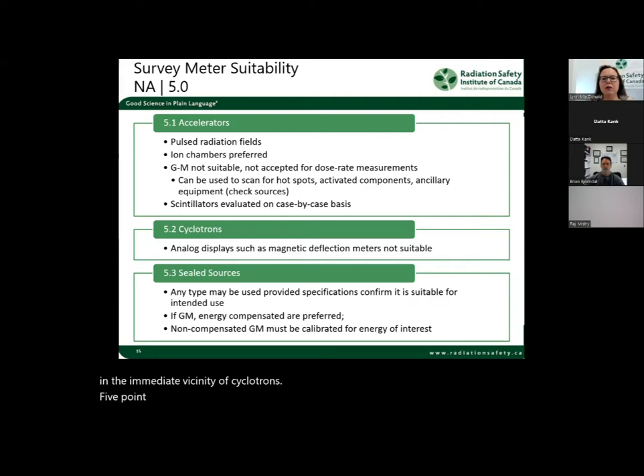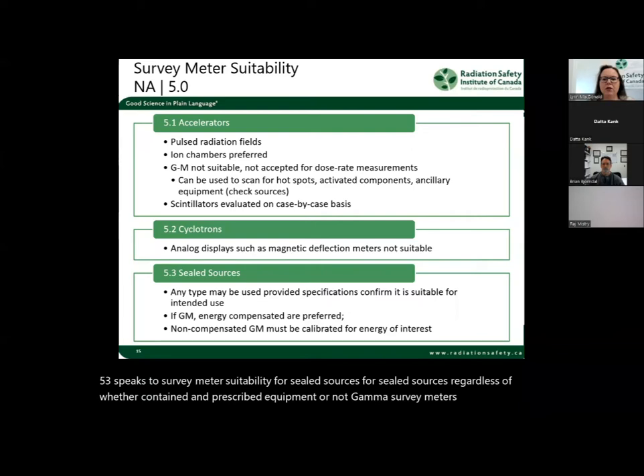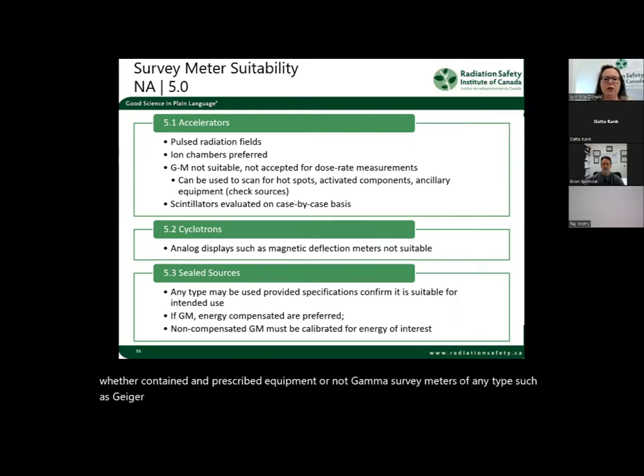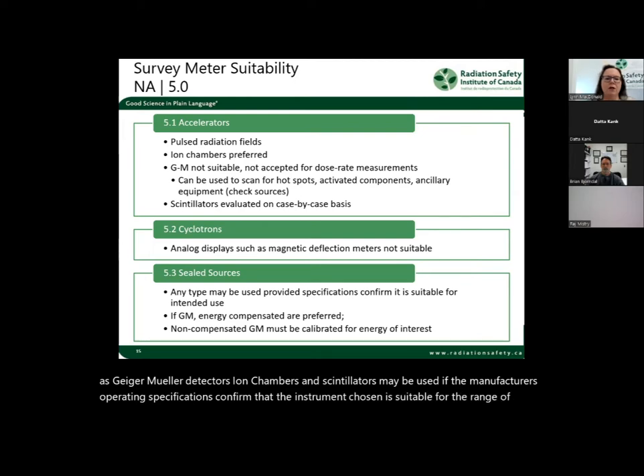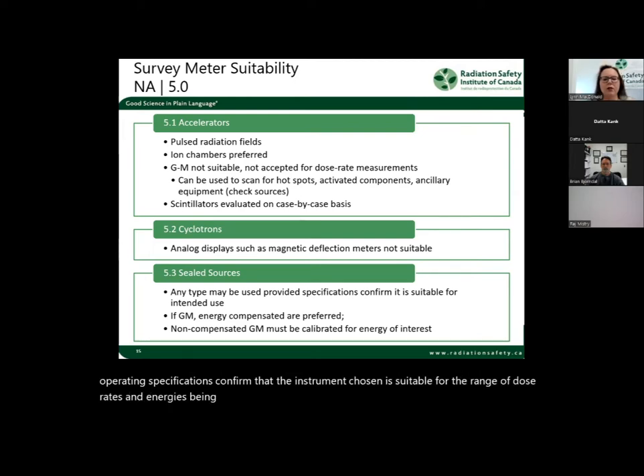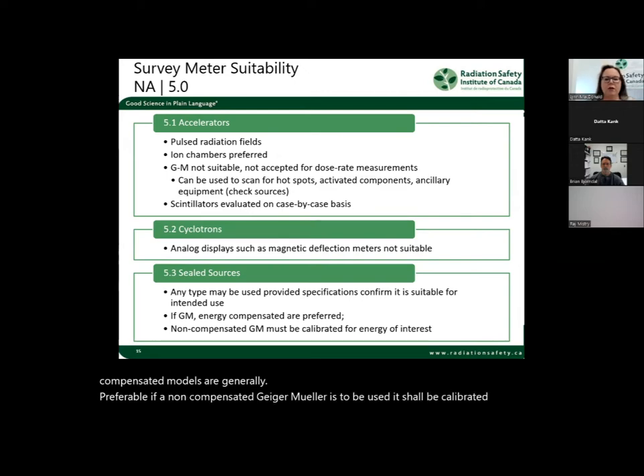5.3 speaks to survey meter suitability for sealed sources. For sealed sources, regardless of whether contained in prescribed equipment or not, gamma survey meters of any type, such as Geiger-Müller detectors, ion chambers, and scintillators, may be used if the manufacturer's operating specifications confirm that the instrument chosen is suitable for the range of dose rates and energies being measured. If a Geiger-Müller detector is to be used, energy-compensated models are generally preferable. If a non-compensated Geiger-Müller is to be used, it shall be calibrated specifically for the energy of interest.